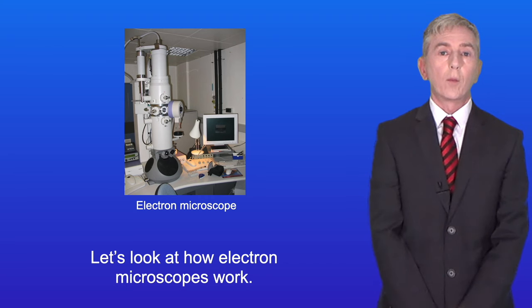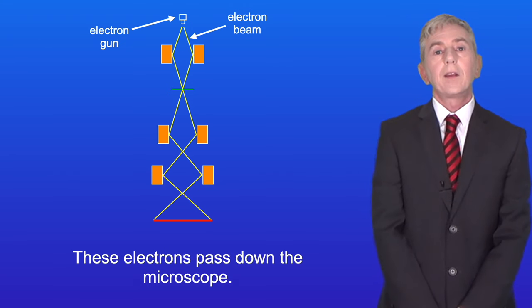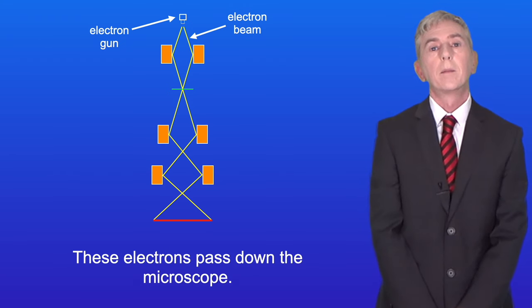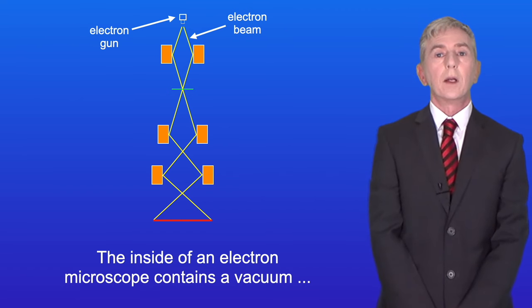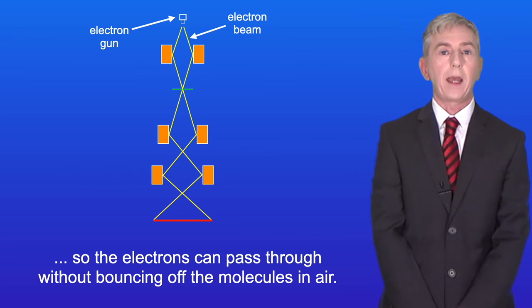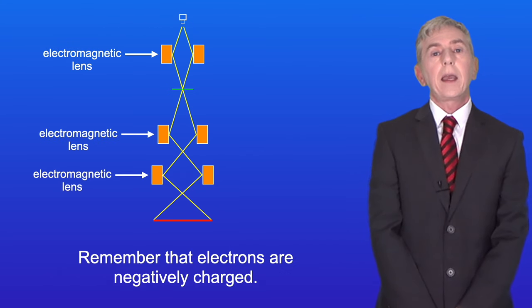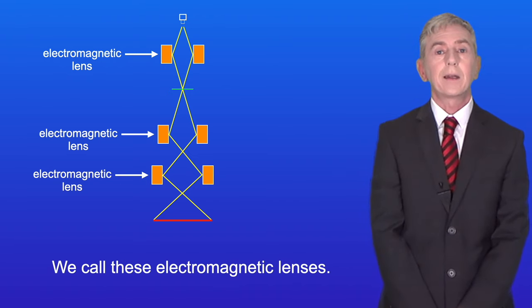Let's look at how electron microscopes work. We start with an electron gun producing a beam of electrons that pass down the microscope. The inside contains a vacuum so the electrons can pass through without bouncing off air molecules. Remember that electrons are negatively charged. This means we can focus the electron beam using electromagnets, which we call electromagnetic lenses.